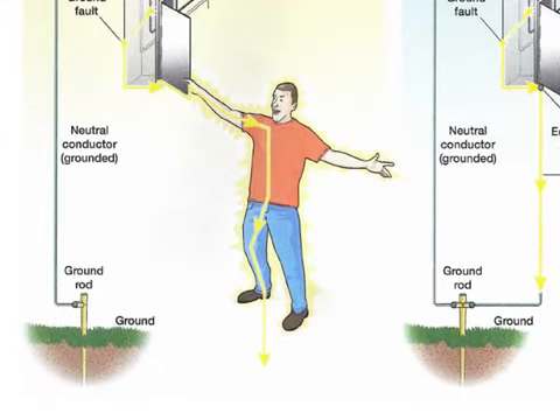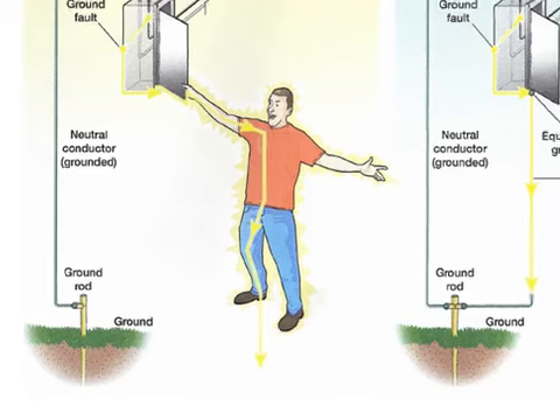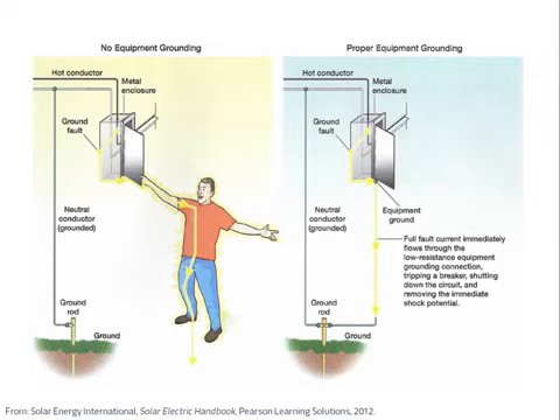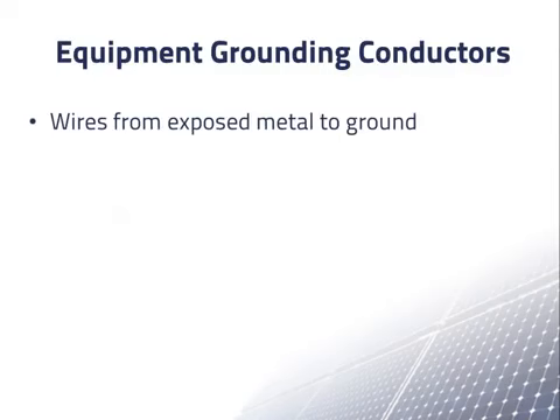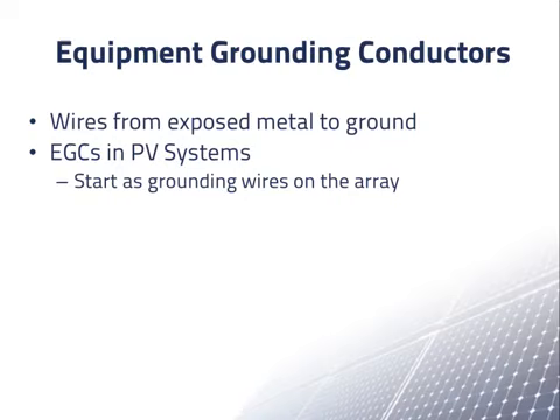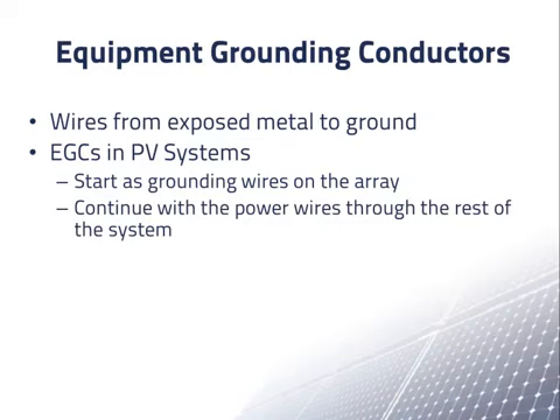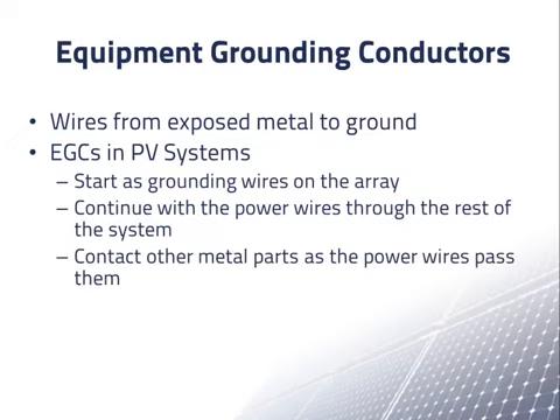At the bottoms of the pictures, we see that an electrical connection to the ground is made through a grounding rod, which is a long metal rod implanted into the earth. The NEC uses the more formal term grounding electrode. A wire from exposed metal parts to ground is called an equipment grounding conductor. This is sometimes abbreviated EGC. In PV systems, equipment grounding conductors are connected to the metal frames and rails in the array. They continue with the power wires through the combiner boxes, switches, and other equipment, and in each component, the equipment grounding conductor makes electrical connection to all metal parts.